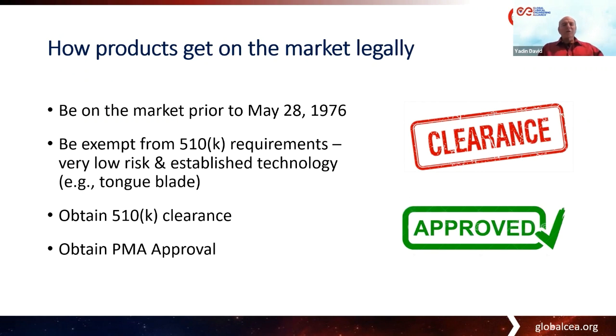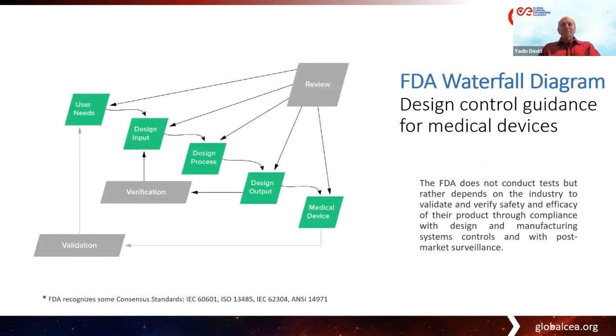There are two routes for products to get to market: one through the 510K, which is clearing, where the FDA is completely dependent on manufacturers to provide all the safety data. The other is through the PMA, pre-market approval process, which provides approval rather than clearance.